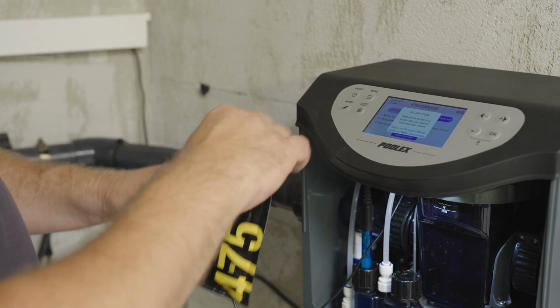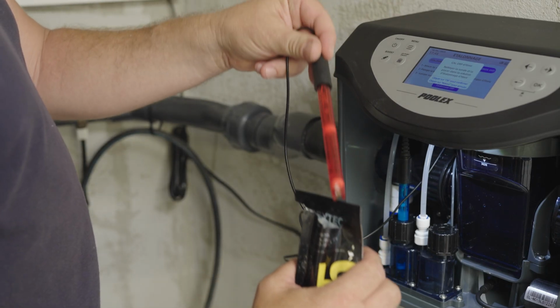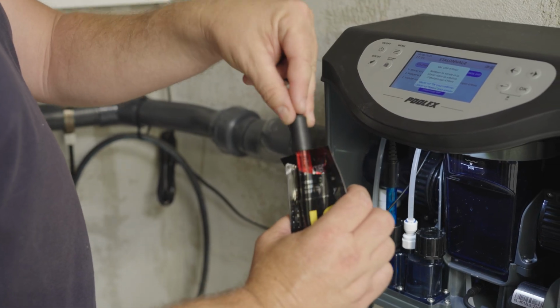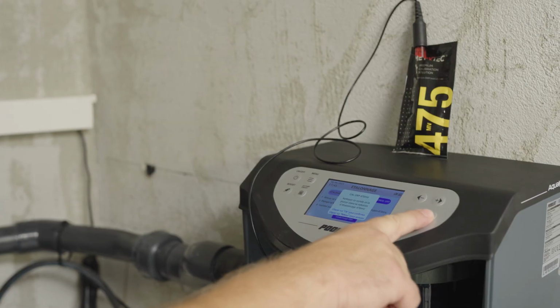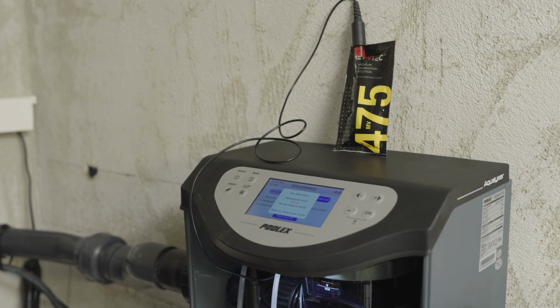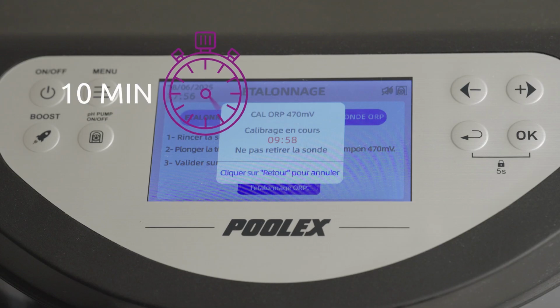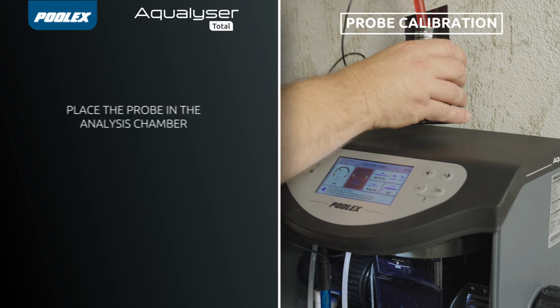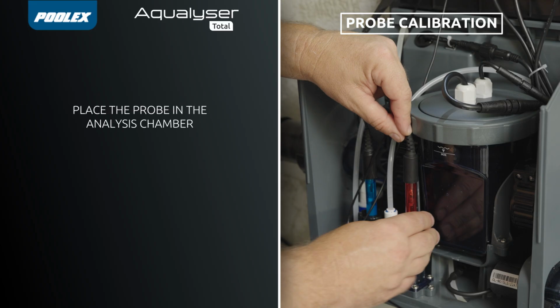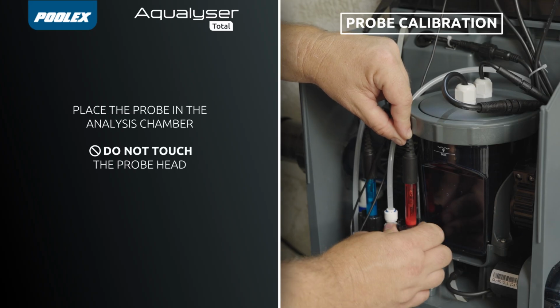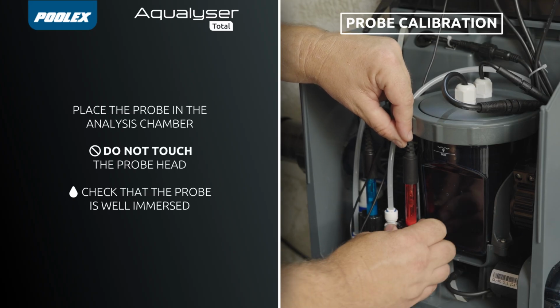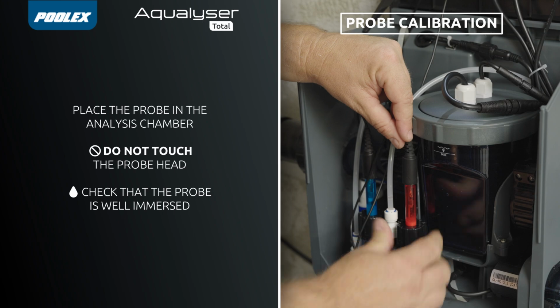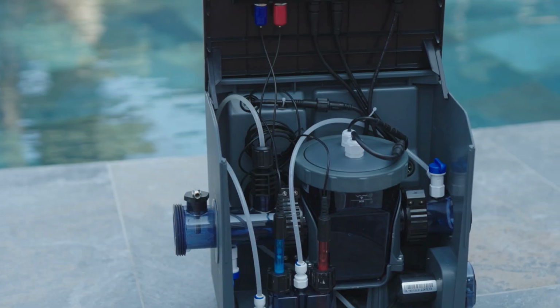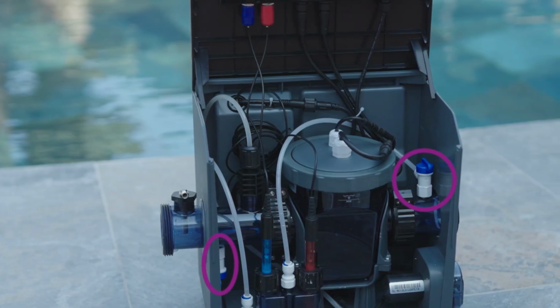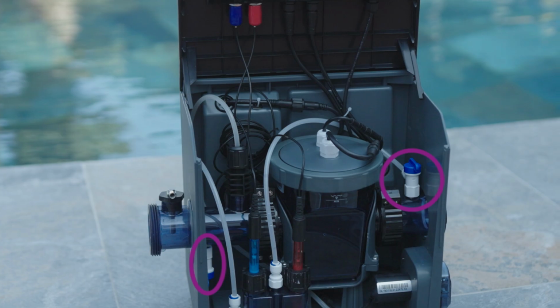Remove the probe from its holder and immerse it in the ORP 475 mV buffer solution. Then press OK. Calibration begins. Leave the probe in the solution for 10 minutes. You can now place the probe into the probe holder of the analysis chamber. Do not touch the probe head with your fingers, and make sure it is properly immersed in water. You can now open the inlet and outlet valves of the analysis chamber to supply it with water.